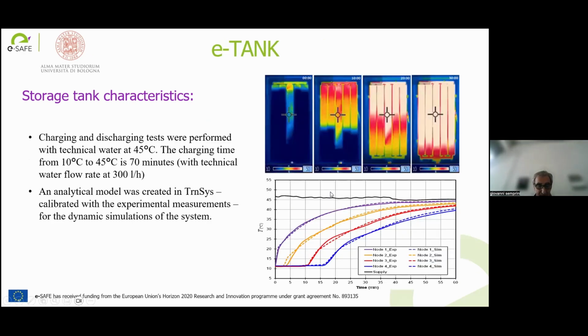In the upper picture, you can see the infrared images during the process of charging the tank. Starting from the central coil, the temperature increases from the higher part to the bottom part of the storage tank. The second picture illustrates the time evolution of the tank's temperature for the case with a mass flow rate of 300 kilograms per hour and a supply temperature of 45 Celsius. The picture demonstrates the transient temperature stratification inside the tank and shows that the full charging process of the tank takes around 70 minutes.